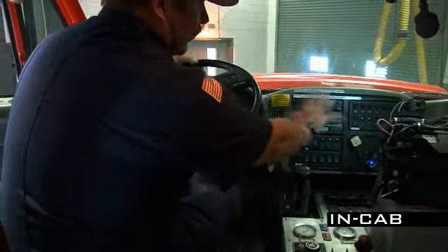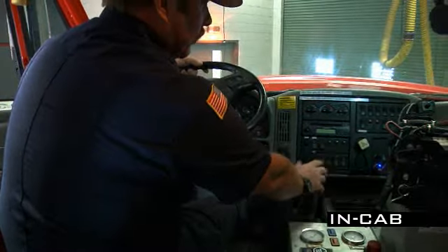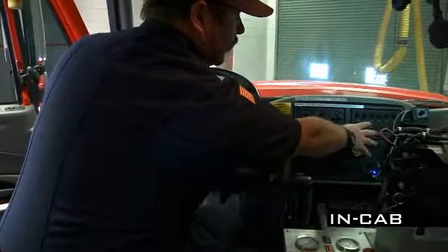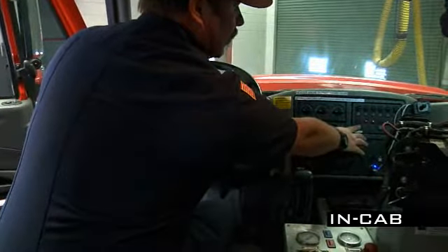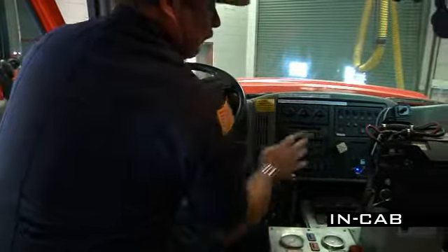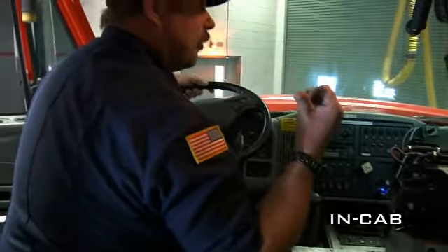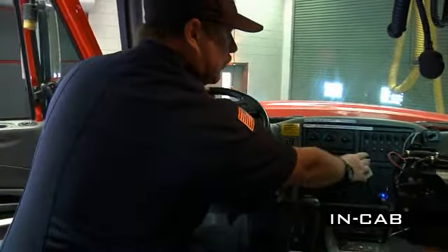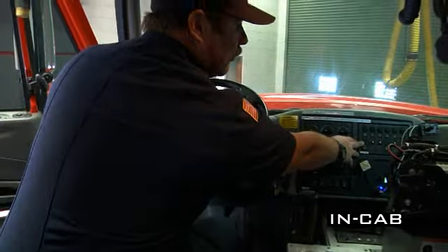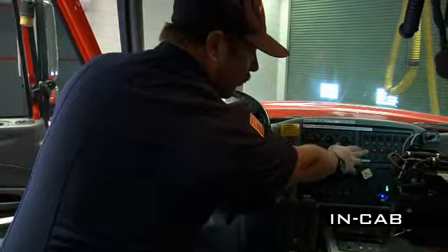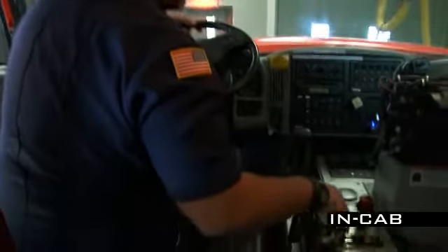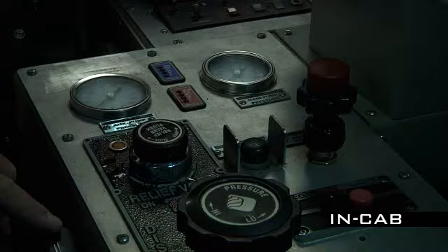But as far as the rest of the pumping operation, you have your auxiliary switches over here. We have the auxiliary pump, okay? Ensuring that your tank to pump is open. You need to depress this switch until you see the pressure come up over here, and always remember to hit the priming button, which is located right here.